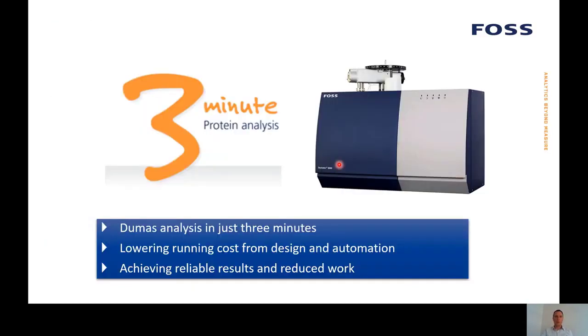So the Dumatec is an instrument that in just 3 minutes does a protein analysis, where you measure on a gas. The element nitrogen will be measured in this instrument. It has a 3-minute runtime if it's a started-up instrument, and you have low running cost and reduced workflow compared to other ways of measuring proteins.